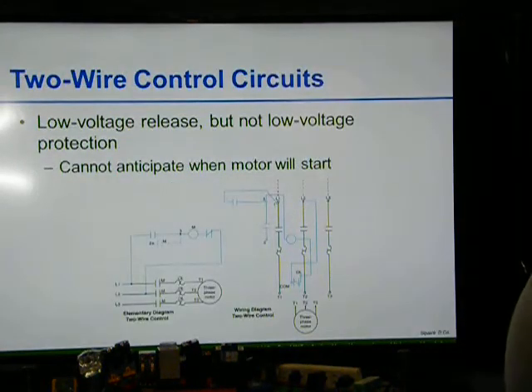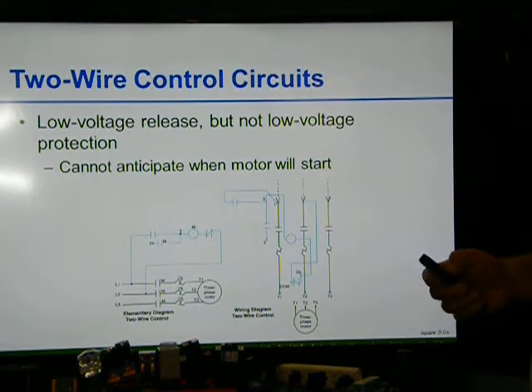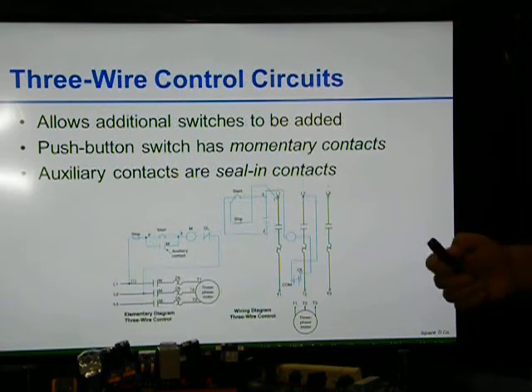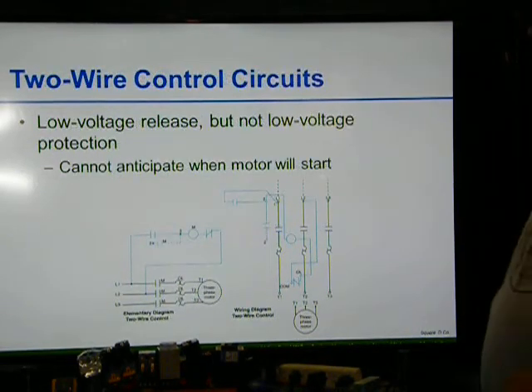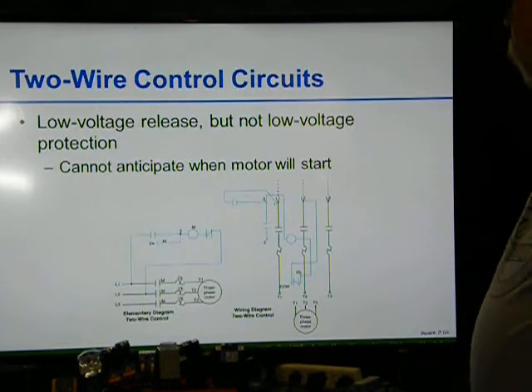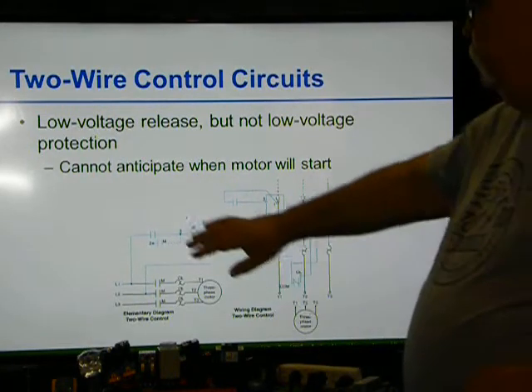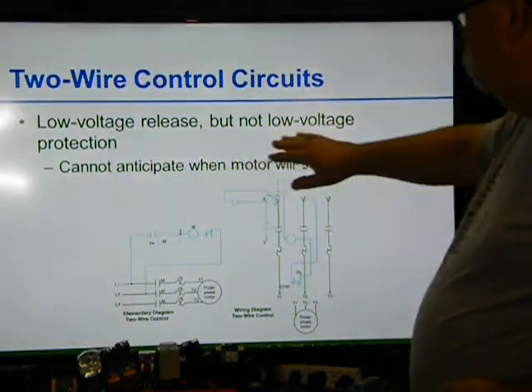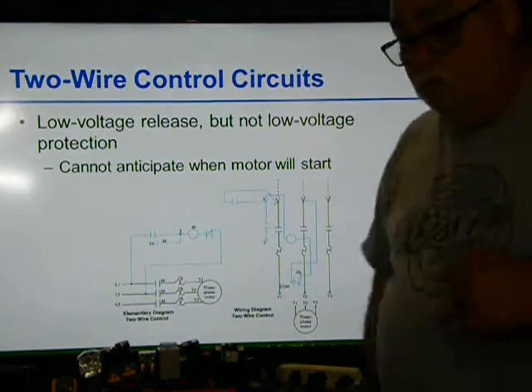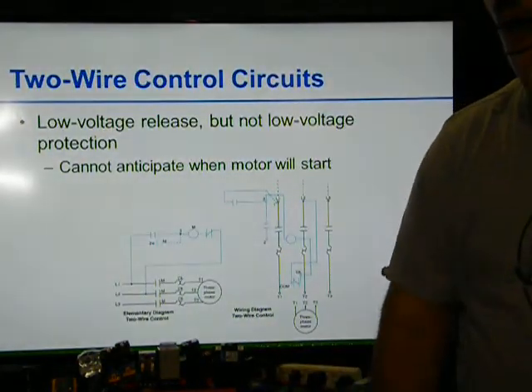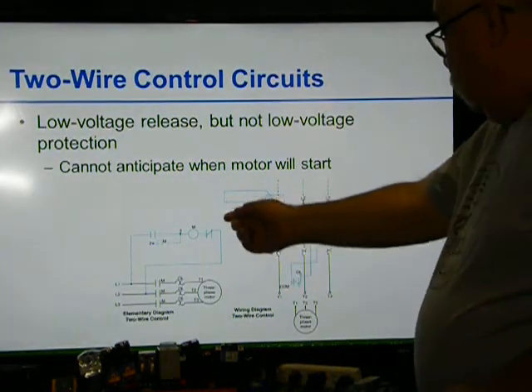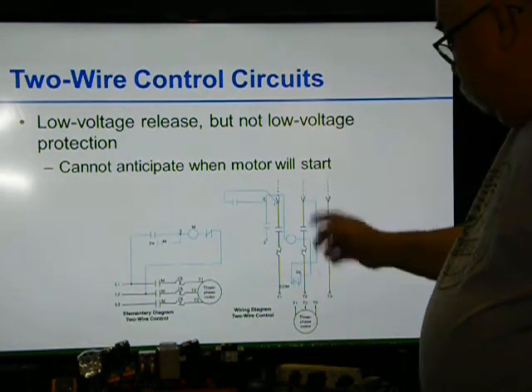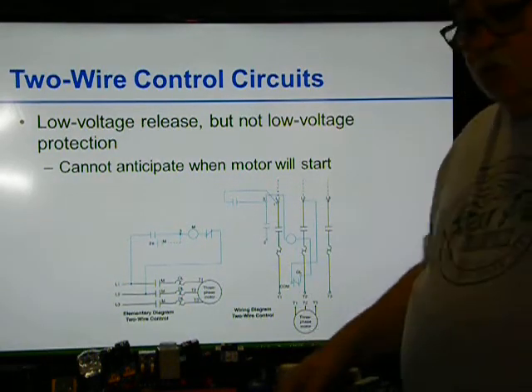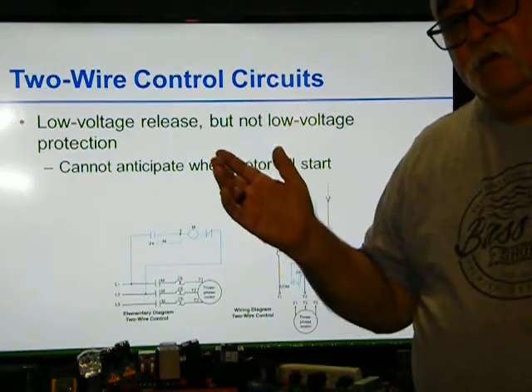Two-wire controlled circuits: this is where I'm going to stop here. I'm going to talk about this before I go into the three-wire. I'm going to talk about two-wire now. A two-wire controlled circuit provides low voltage release, but not low voltage protection. What does that mean? Like I was talking about earlier, I turn the switch on, this motor comes on, and guess what? Power goes out.